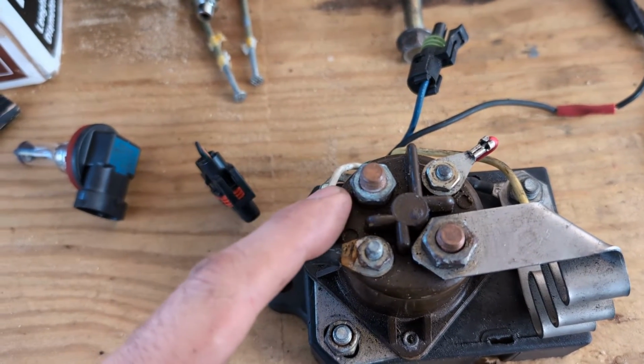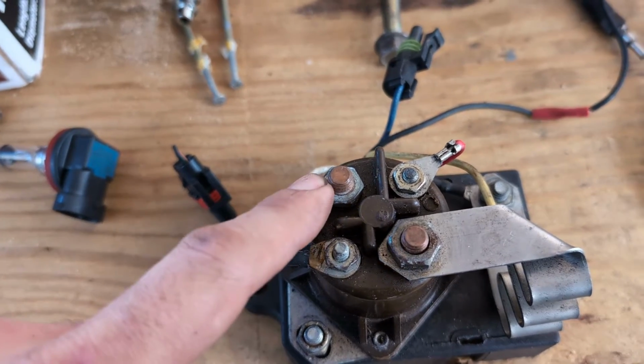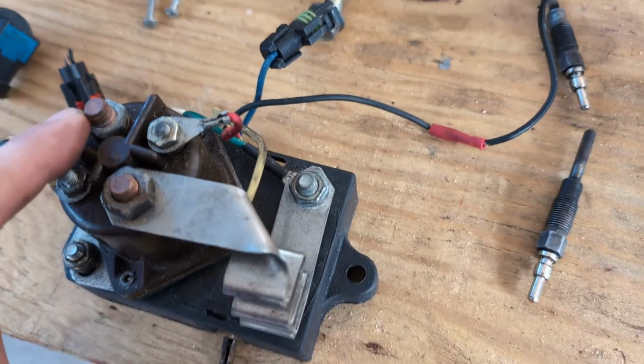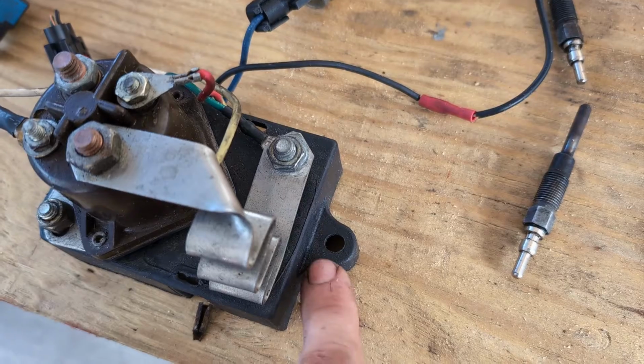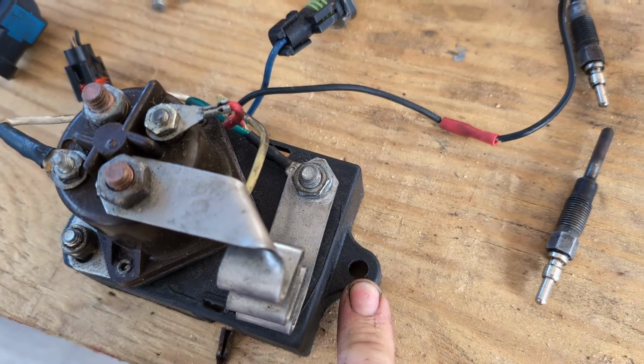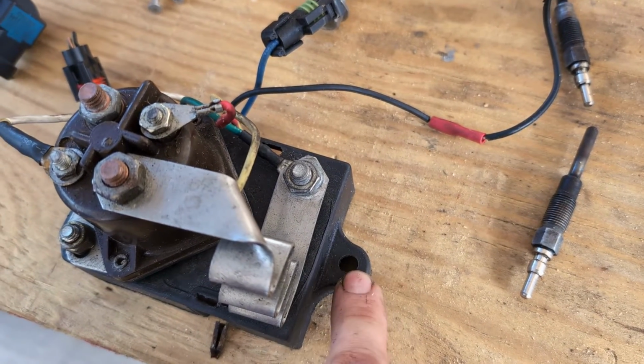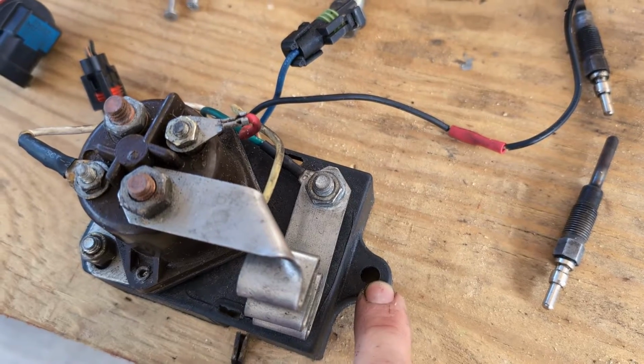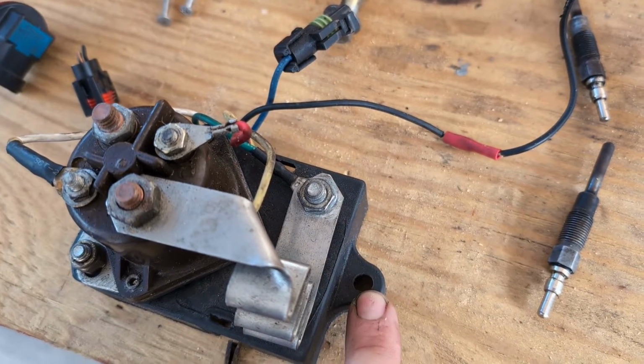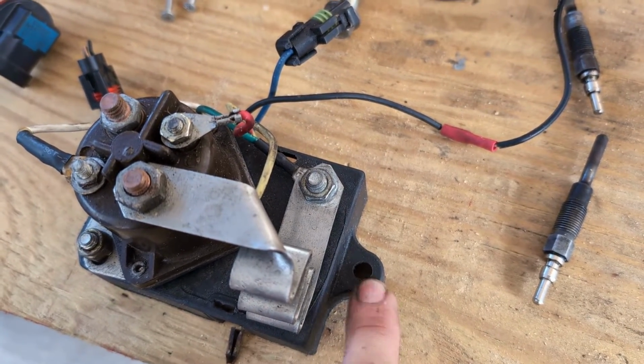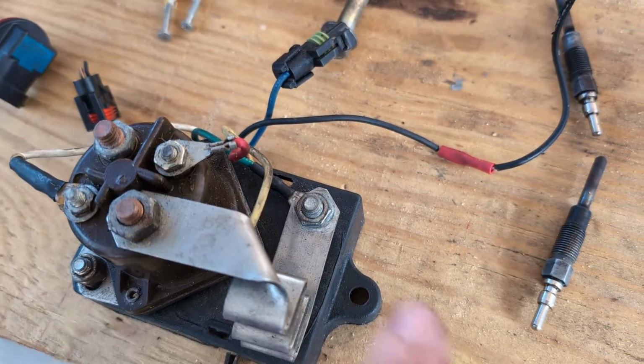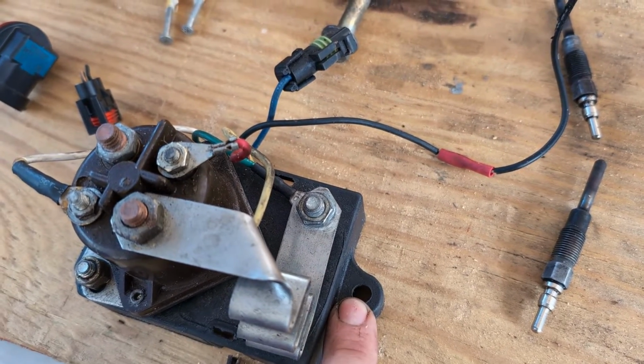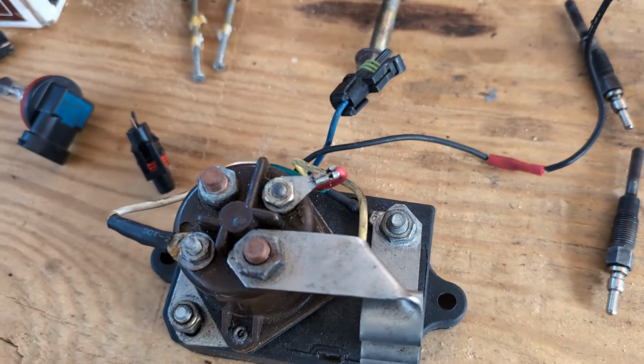So what we're going to do is put one probe here, and our other probe is going to go here, because this is where that ground is tied in, and we want to see battery voltage. So we want to see around 13 volts when we check voltage between here and here, and that will ensure that we're getting power.